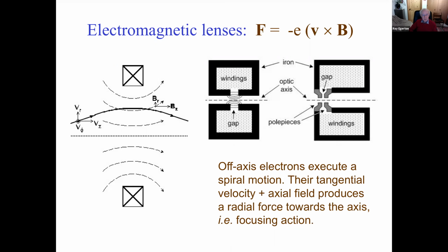Once we have that perpendicular component of motion, then that component of v combined with the magnetic field along the axis gives us a force back towards the optic axis. And so we have our electron deviating from the axis and then focused back towards the axis, and that's the basis of the focusing action. We can make it more efficient by surrounding the windings which provide this magnetic field with ferromagnetic material, with a small gap that concentrates all the magnetic field into a region a few millimeters cubed on the optic axis.